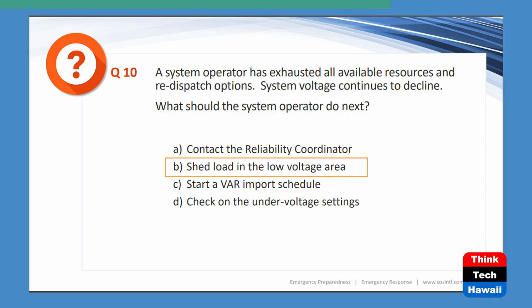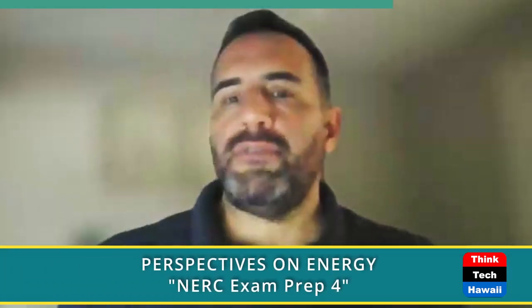So the correct answer here really is shedding load in the low voltage area. Once you do that, the load being shed in that area will improve the voltage profile on that area that's deficient and showing that decline in voltage. So that's really the best answer and the correct answer in this case. Now, of course, there are other options as well, which I don't show here. If you had capacitor banks out there, I would deploy capacitor banks. I would change taps on transformers. I would try and bring on additional generation in this case. I would make sure that I have taken all the other reactive devices out of service. Those usually are there to bring down voltage. Now, that's happened before. I've seen some of them leave a reactor in service during the peak of the day.